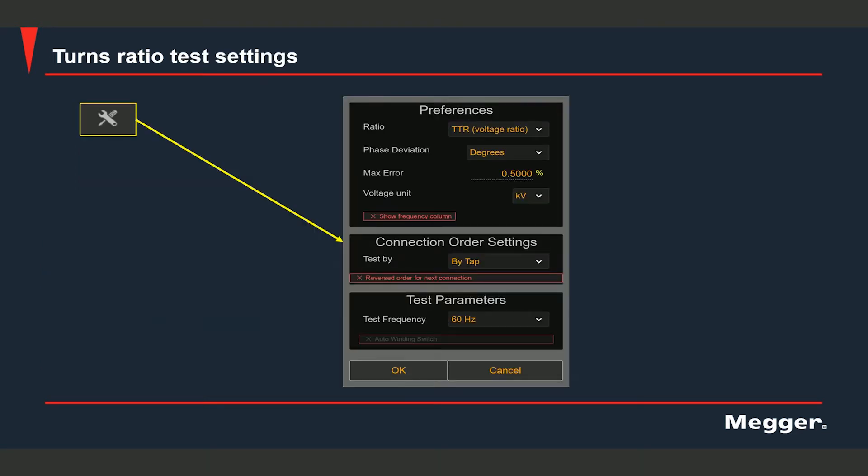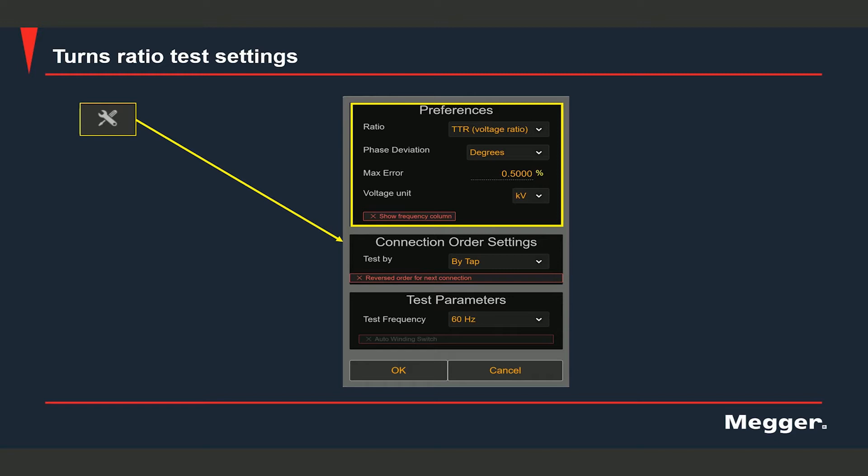If you select the test settings option, this is the window that would come up. Let's go over each of these points. Under preferences, you have ratio display parameter. Do you want to see the turns ratio? Or do you want to see the nameplate ratio? Phase deviation can be displayed either as degrees or radians or centiradians. You can also see the maximum acceptable percentage ratio error limit, which is set at half a percent. Voltage unit is set to KV, and those are the units in which the rated voltages would be displayed in the app. There's also a checkbox to enable or disable the frequency column.